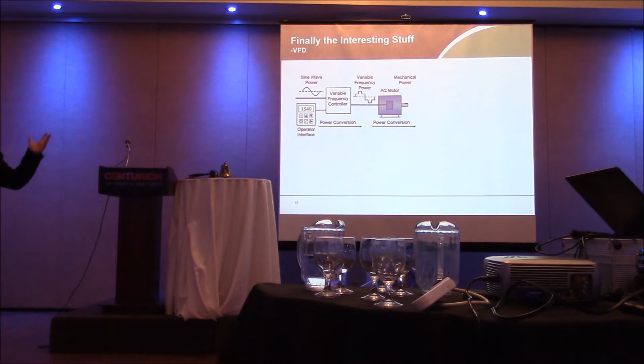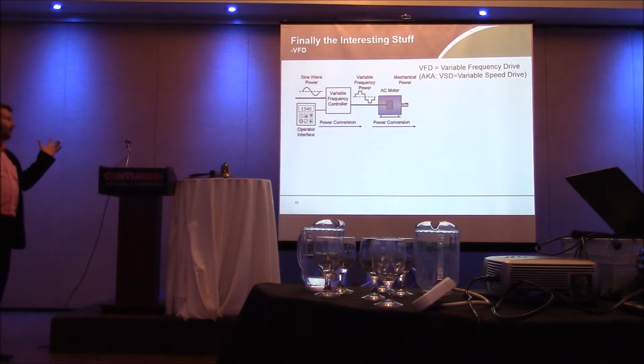Drives. Everybody loves drives. Because drives make all your problems go away, right? Except for the problems that make themselves. Bigger the motor, the bigger the drive. Just like the starter. Operating a motor at less than 60% of full load speed, unless the motor is specifically designed for it, will probably overheat the motor. So think about something else when you're doing that. It's also not very electrically efficient.